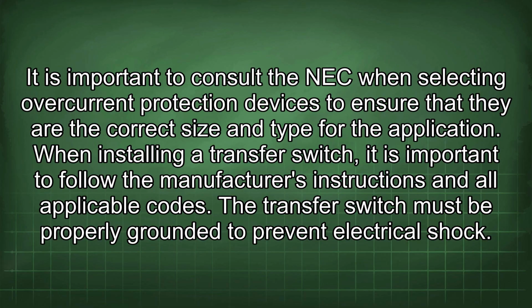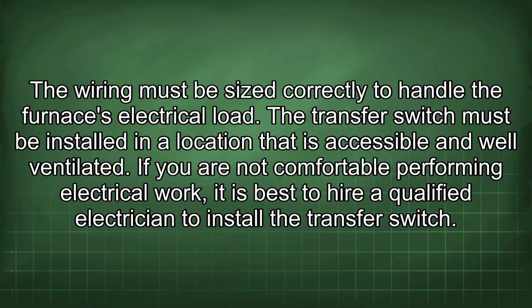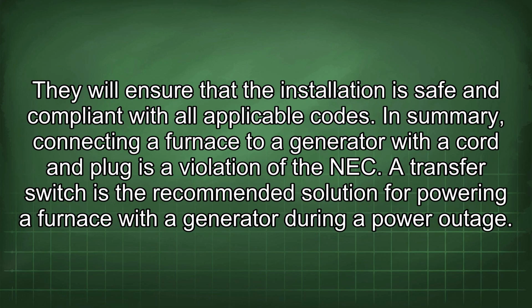When installing a transfer switch, it is important to follow the manufacturer's instructions and all applicable codes. The transfer switch must be properly grounded to prevent electrical shock. The wiring must be sized correctly to handle the furnace's electrical load. The transfer switch must be installed in a location that is accessible and well ventilated. If you are not comfortable performing electrical work, it is best to hire a qualified electrician to install the transfer switch. They will ensure that the installation is safe and compliant with all applicable codes.